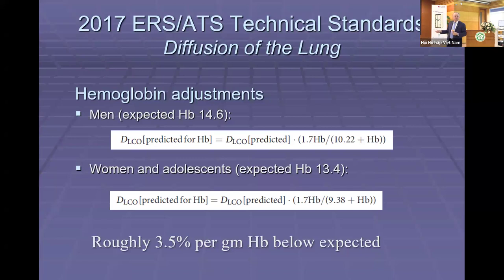There are a few adjustments that we have to make to the value based on what we know. The first is hemoglobin. If someone is anemic or polycythemic, they'll have either more or fewer sites for the CO to attach to. We need to know someone's hemoglobin level to get a correct value. The systems default to normal values of 14.6 for men and 13.4 for women. If significantly different from that, the test should be adjusted for polycythemia or anemia.